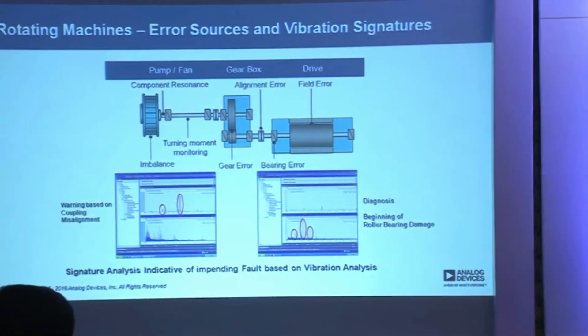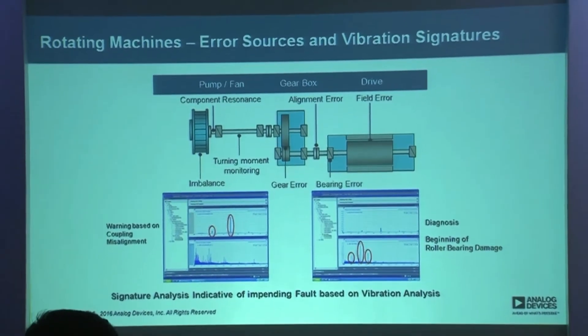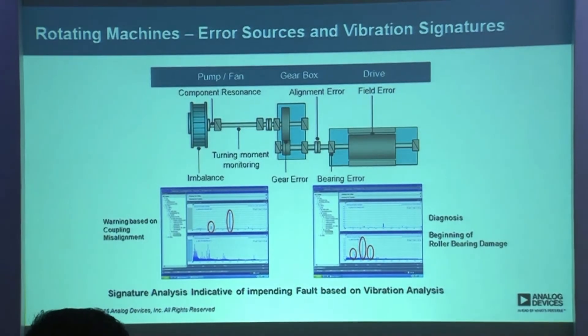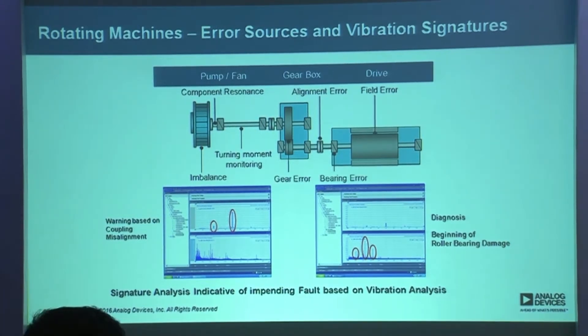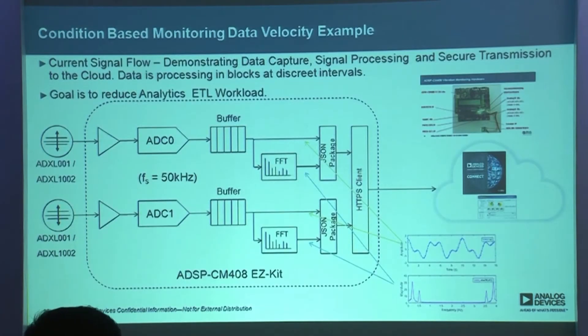In rotating systems, we saw opportunities to improve the quality of how pumps and rotating machinery can be monitored. If you look at motors today, whether it's a pump or a fan, there are various types of faults — in bearings, couplings, imbalances in loads — that can be monitored. These artifacts show up very well in the frequency domain: different harmonics and tones start to appear, which can be leading indicators of a potential problem. We have our ADXL sensor, a very wide bandwidth sensor developed just for this application, and it's starting to replace even piezoelectric-type sensors in some applications as MEMS sensor performance improves.